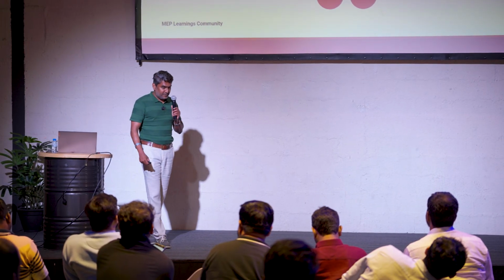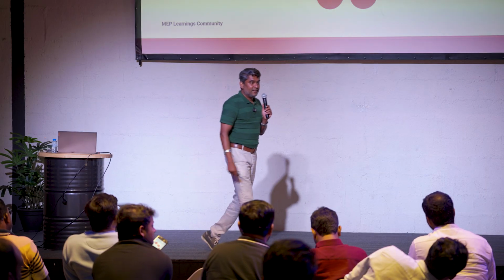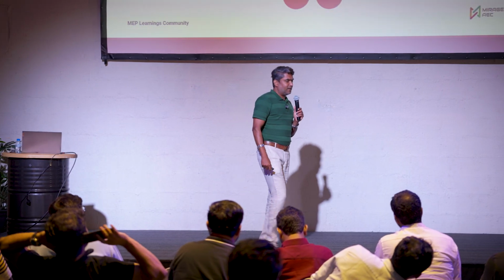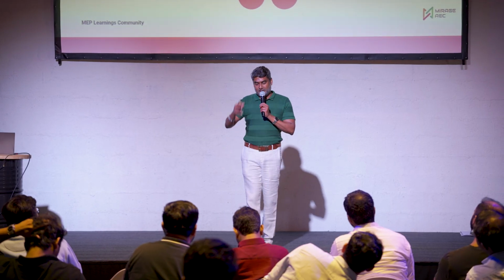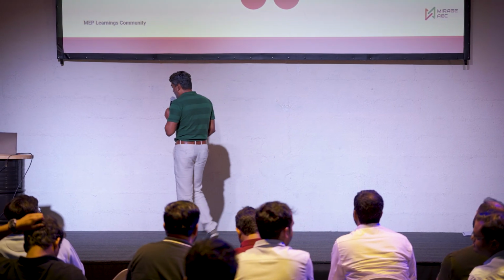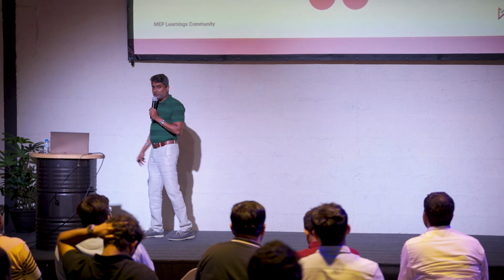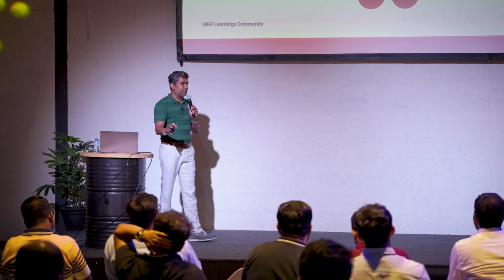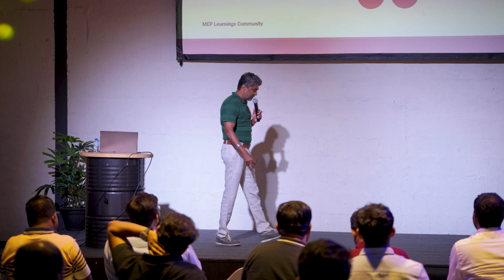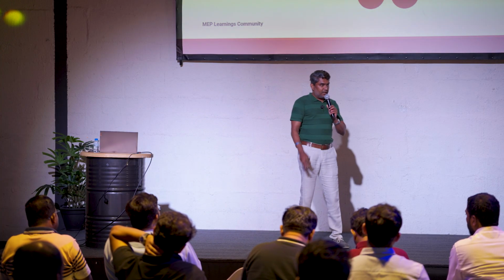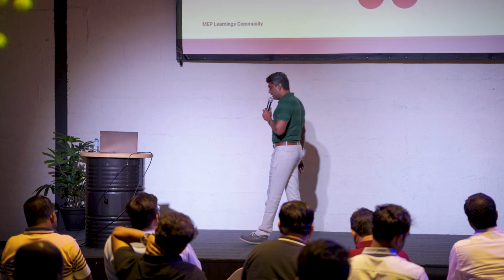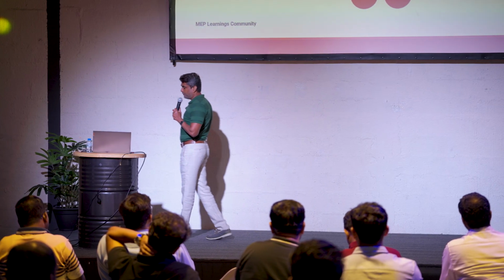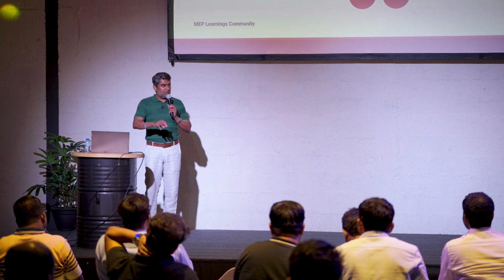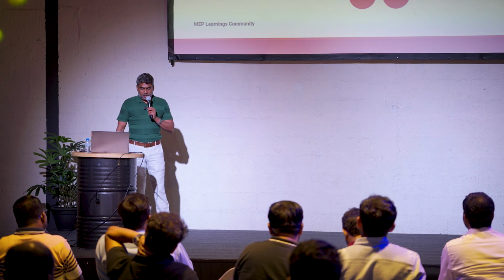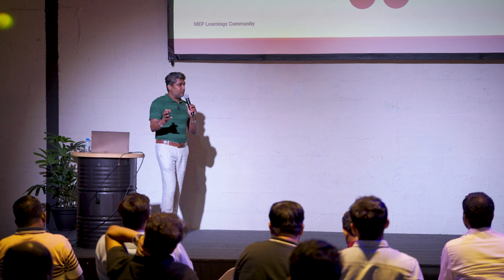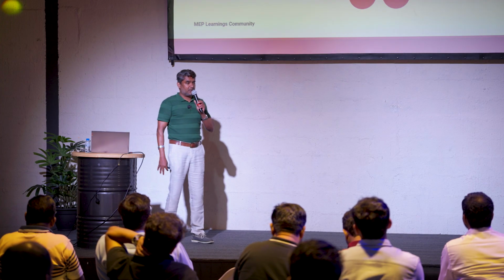FAHU. Exactly, that's the most important point. Any fresh air you're feeding to the floor is actually going to feed the fire, so oxygen has to be cut off from the floor. That's why all the FAHUs or extract fans need to be addressed. While the extract fan is running, it will try to pull fresh air from some other area, so that system has to be cut off. If you think about it, all of this comes under the category of safe evacuation.